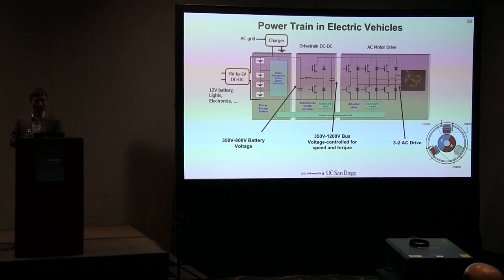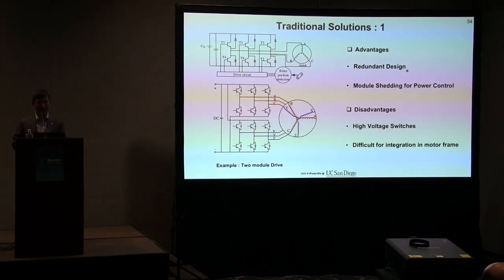So the active switching components for the motor drive—silicon carbide is now relatively new in the last 10 years, but it's actually standard in motor drives now. But silicon carbide cells have their own limits. Going to high voltage gives a lot of stress to these AC motor drives. In this traditional solution, it works great and you can put more devices in parallel, but high voltage is still the underlying theme.